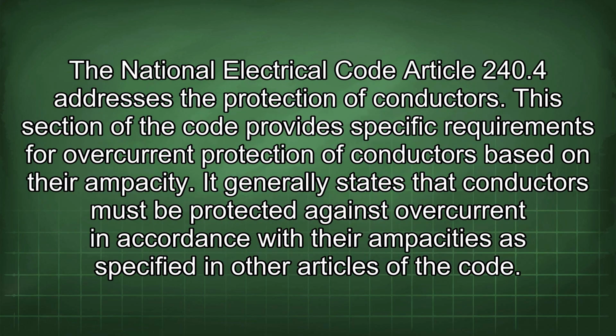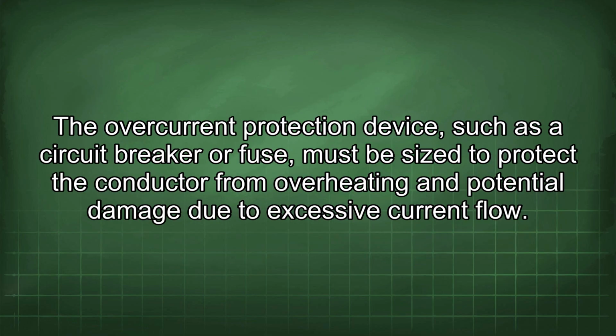The National Electrical Code Article 240.4 addresses the protection of conductors. This section of the code provides specific requirements for overcurrent protection of conductors based on their ampacity. It generally states that conductors must be protected against overcurrent in accordance with their ampacities as specified in other articles of the code. The overcurrent protection device, such as a circuit breaker or fuse, must be sized to protect the conductor from overheating and potential damage due to excessive current flow.